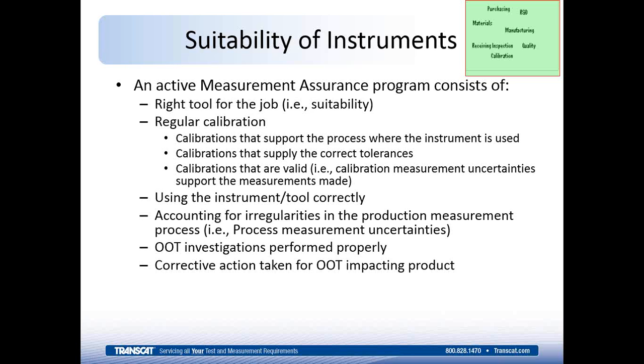So even if you had this whole traceability chain that's done with healthy ratios all the way through, and your process accuracy ratio is healthy, if you find out of tolerances on the instruments that are being used in the production line are not being investigated properly, or if they're not being done at all, then you just really threw the whole traceability chain out the window. So that's a very important thing to consider. And then once you find an out of tolerance, is the corrective action being taken to make sure it's not impacting product? That's really what the whole traceability chain is for, to make sure that you didn't make the wrong decision about product being pass or fail, and that the instrument being used didn't impact that as well.